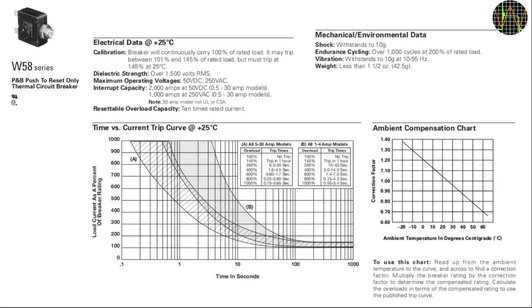This kind of breaker has the usual bimetallic contact that will eventually trip if sufficiently heated through the overload current but that process is relatively slow. To make it trip quickly at spikes and shorts, there is an additional electromagnet inside that opens the contacts when the current and therefore the magnetic field exceeds the threshold.